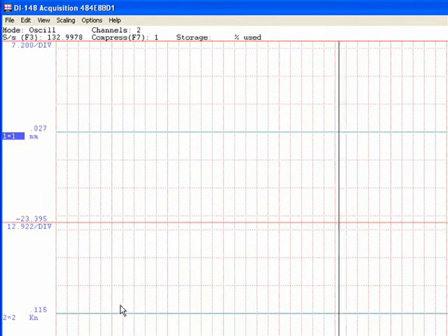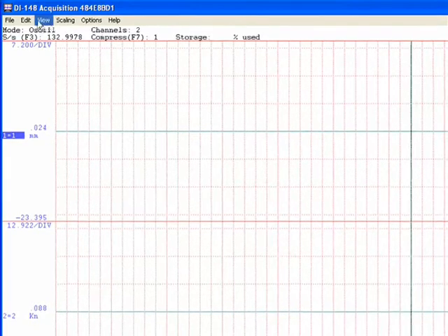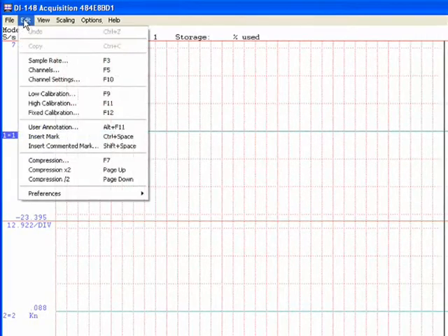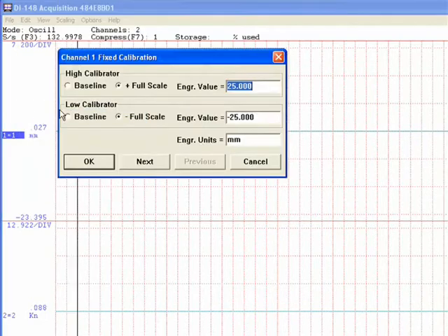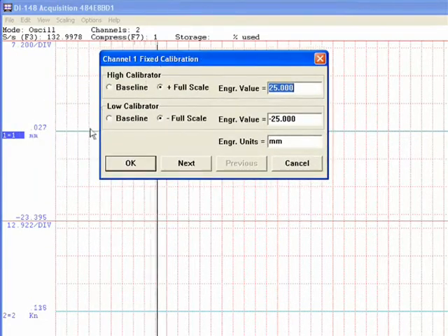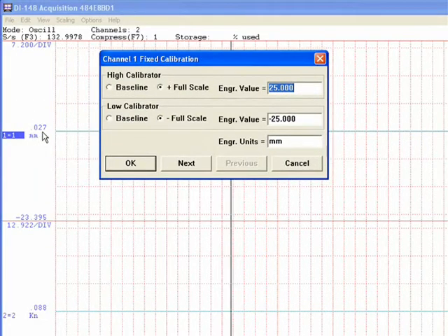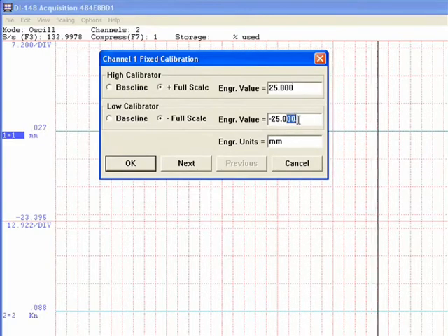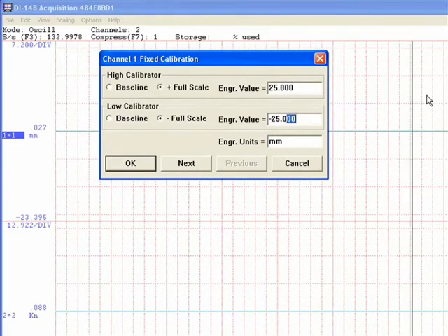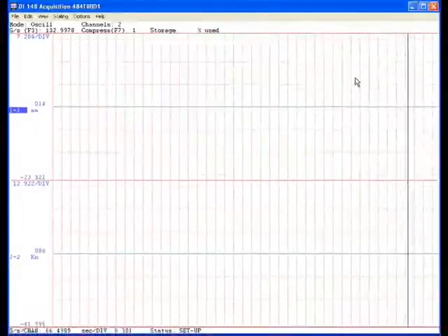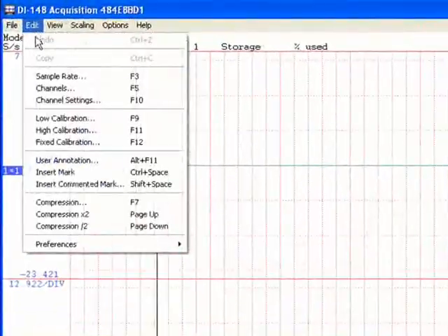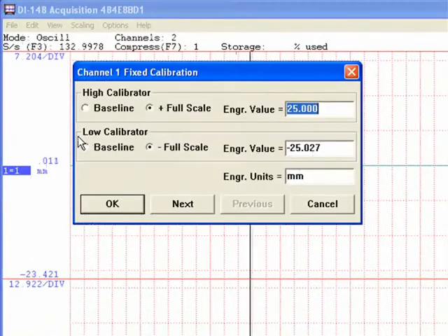Make sure your meters are both reading zero. Go back into Edit, Fixed Calibration. And I'm going to change this slightly to bring it to zero. And it doesn't take much, you just have to play with it, but you only have to do this one time.